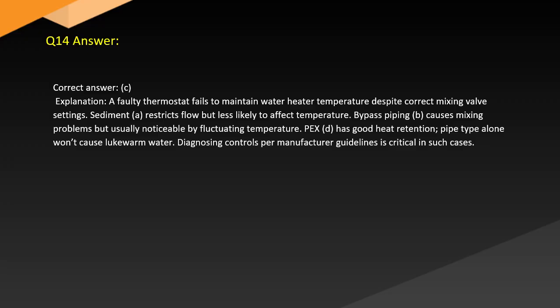Answer. Correct answer: C. Explanation: A faulty thermostat fails to maintain water heater temperature despite correct mixing valve settings. Sediment (A) restricts flow but is less likely to affect temperature. Bypass piping (B) causes mixing problems but is usually noticeable by fluctuating temperature. PEX (D) has good heat retention. Pipe type alone won't cause lukewarm water. Diagnosing controls per manufacturer guidelines is critical in this case.